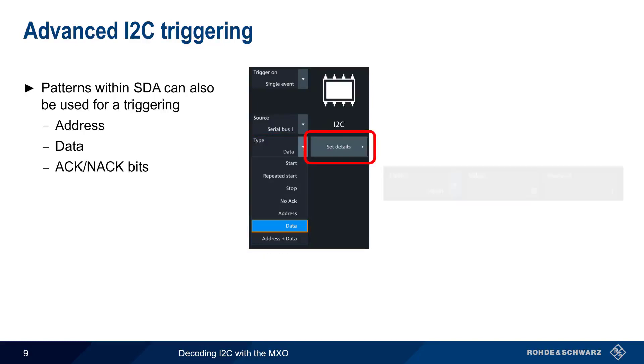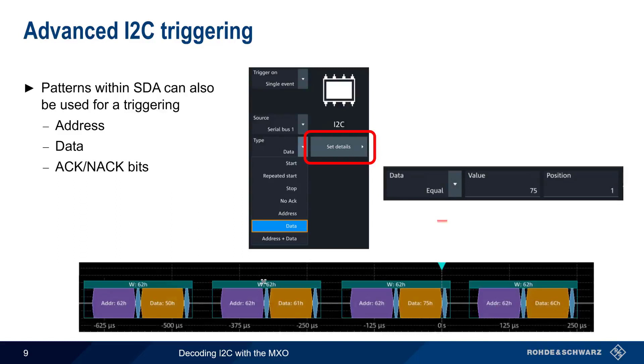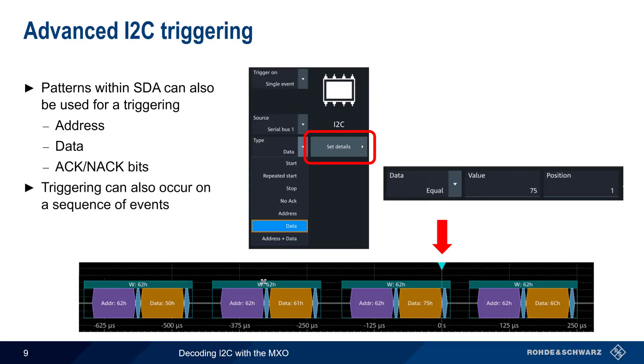Here, we're configuring the MXO to trigger when it sees a frame containing 0x75 as its first data byte. In addition to single events, the MXO can also trigger on a sequence of events. Please see the user documentation for more details on how to configure a sequence-based trigger.